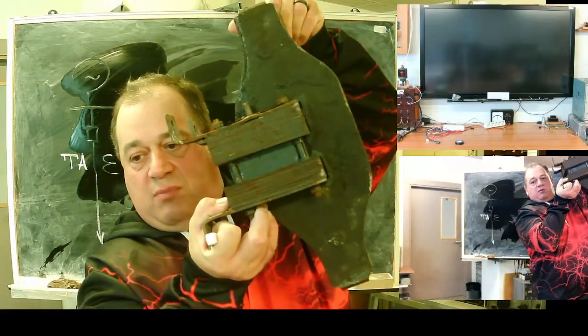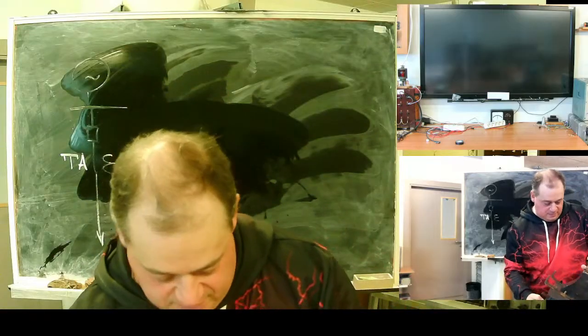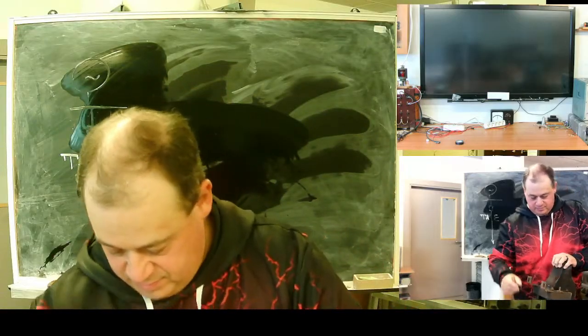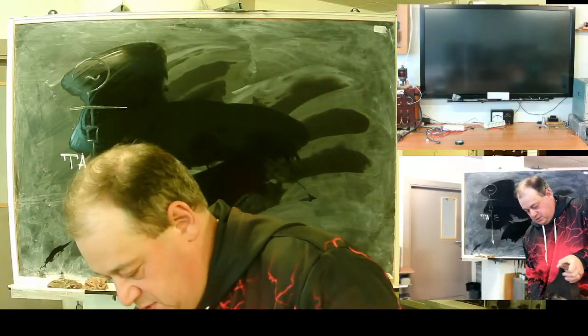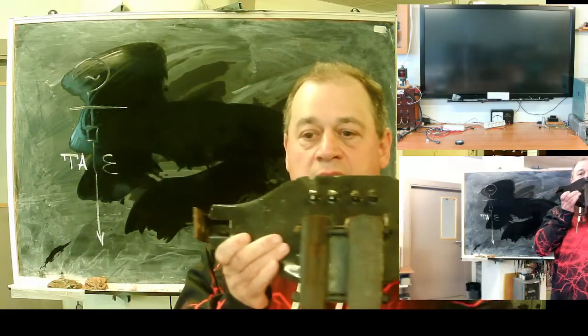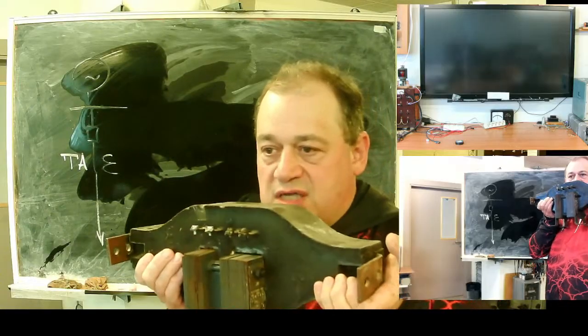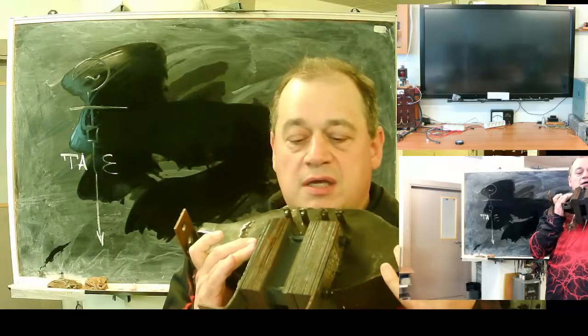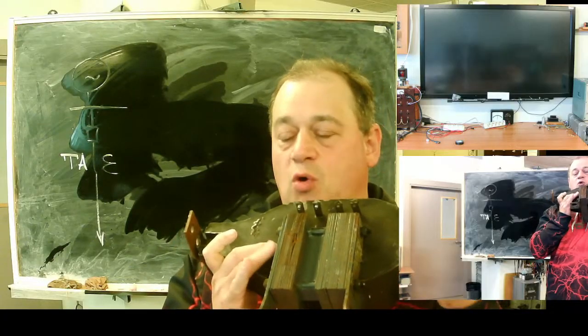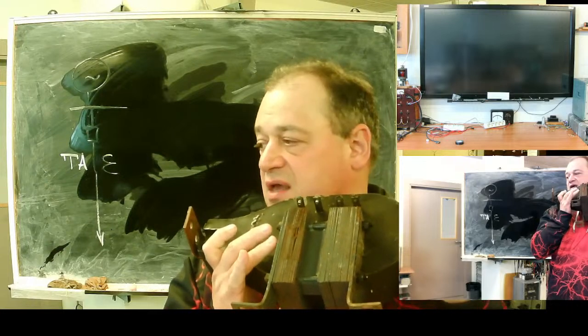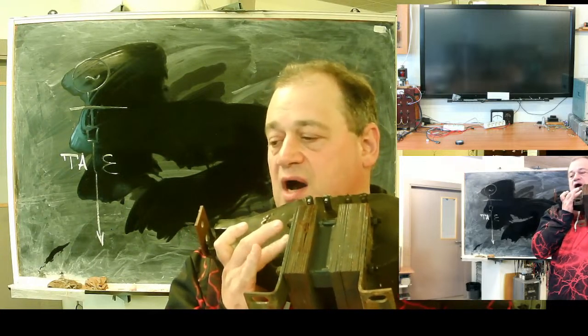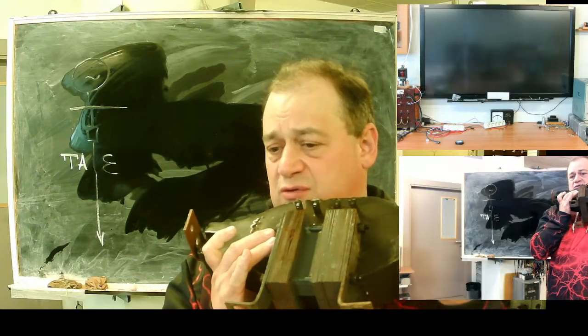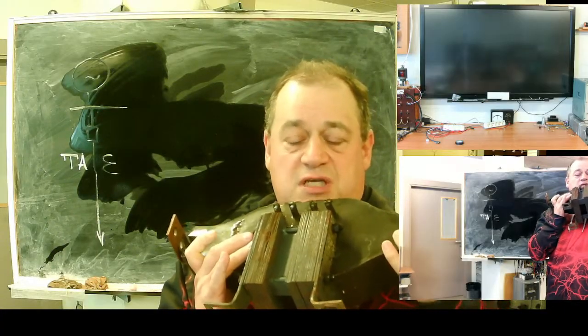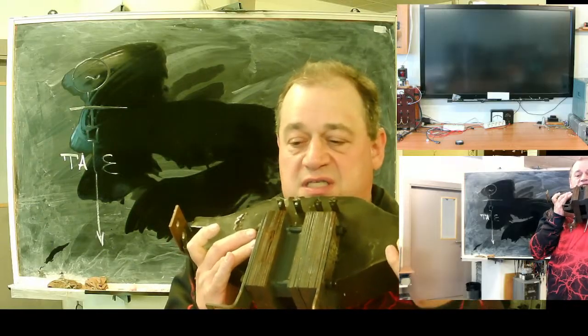10 current transformer for 10 kilovolts. It has 2 cores, you see? One, the bigger one, is for protection, the smaller one is for metering. This one is precise, but it's only operational up to approximately 150% of rated current. Then it will saturate. The large one is less precise, but it's operatable up to 40 times rated current.